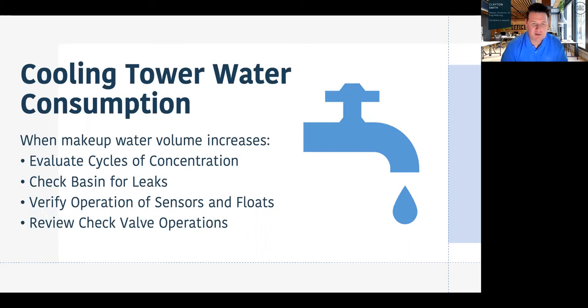Verify operations of sensors and floats. Go back to calibrate your sensors. Stay on top of your sensors. Make sure that we are using the right amount of water. Is it your basin float? Is it the flow sensor? What are those things? That's really me on my soapbox of calibrate and verify your sensors. And then last, review your check valve operations, making sure we're not losing water back into the system. Next slide, please.